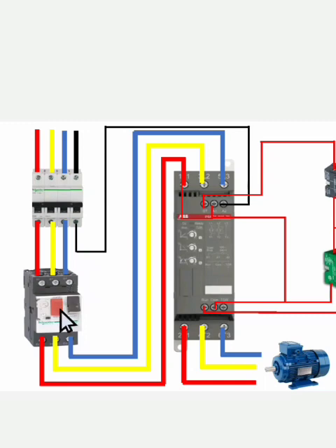Here we set the current rating of the motor. This MPCB helps protect the motor. If the motor is rated 20 amps, you choose an MPCB with a range of between 17 and 24. There are standard values, so you just select an MPCB whose range your motor's current falls within. You adjust the slider here to match the current of your motor.